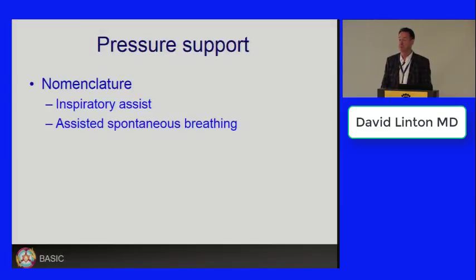And it works beautifully if the machine has a very good demand valve, if the flow characteristics of the demand valve are good, and if there's enough flow in the system. Because if the patient wants pressure support and they have to suck very hard to get the air, or the machine doesn't trigger very quickly, the patient gets uncomfortable. So pressure support is all very well, but it has to be delivered by a good machine. And that's the problem, because some machines give good flow and some don't.